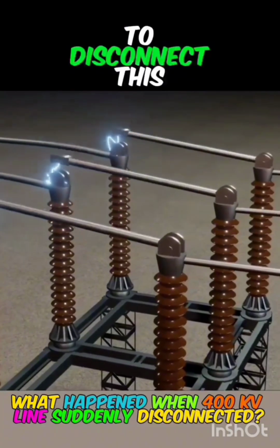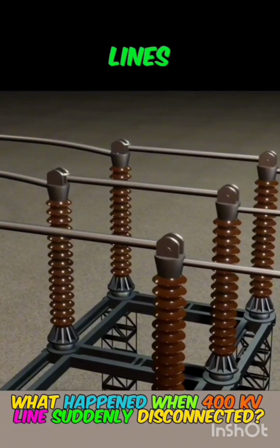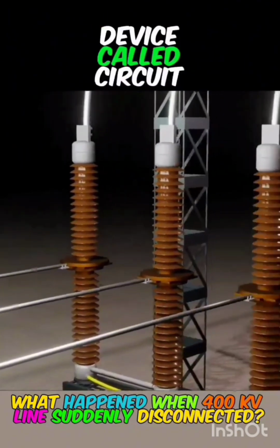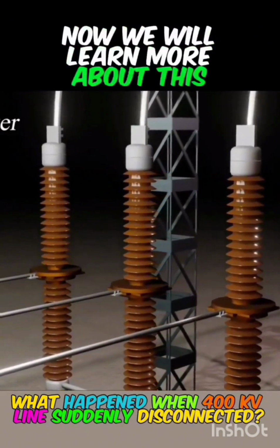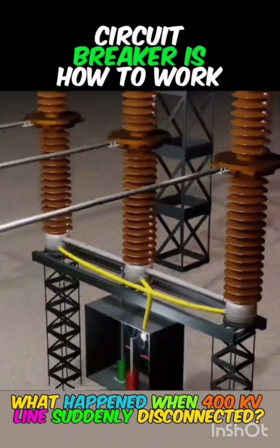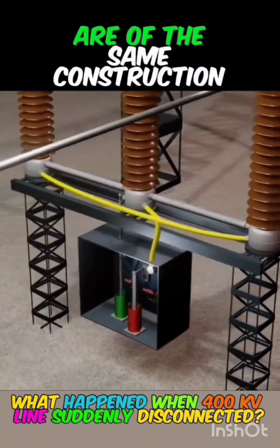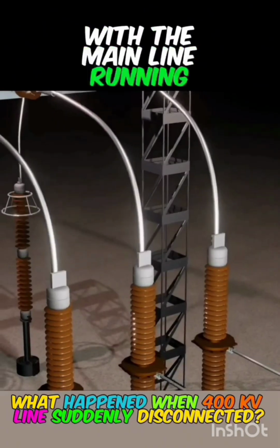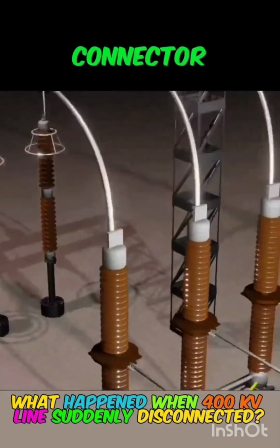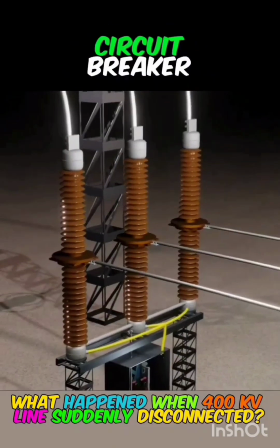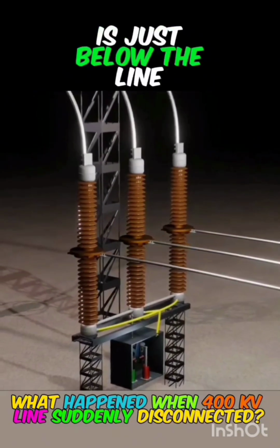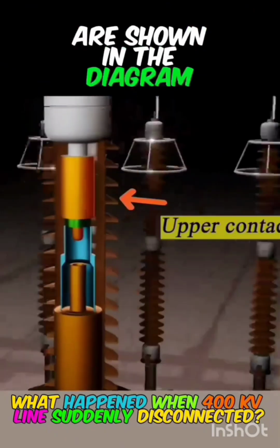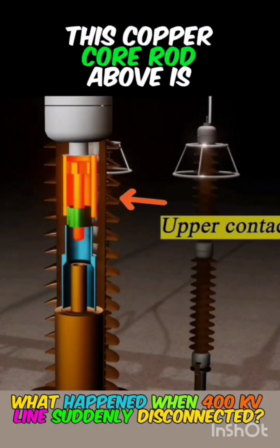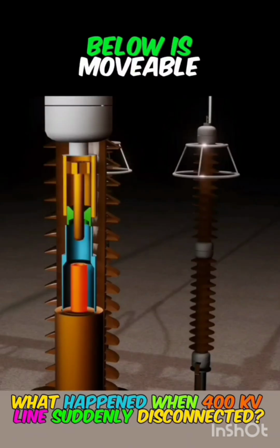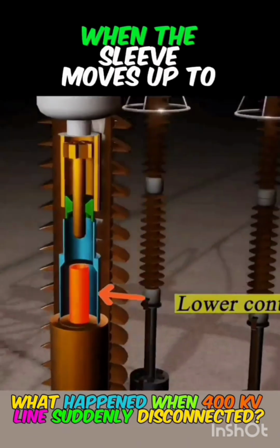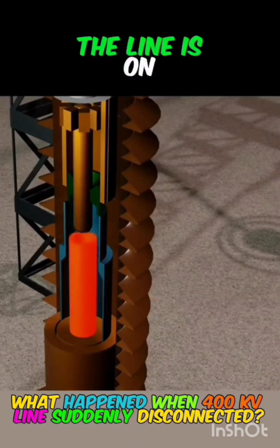Therefore, to disconnect this 400,000-volt high-voltage line, you usually need to use a special device called a circuit breaker. Now we will learn more about how this SF6 gas circuit breaker works. All three-phase circuits are of the same construction, with the main line running down from above, passing through an internal connector and out from there, and the mechanical part of the circuit breaker controlling the circuit is just below the line, and its internal connections are shown in the diagram. This copper core rod above is fixed, while this copper sleeve below is movable up and down. When the sleeve moves up to insert the copper rod, the line is on.